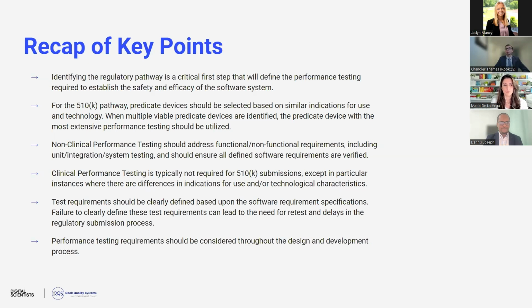So depending on the risk level of your device, your burden as far as providing data related to the non-clinical performance testing shifts a little bit. But at the end of the day, everybody should be performing that unit, integration, and system level testing. It's just a matter of what goes in front of the FDA.